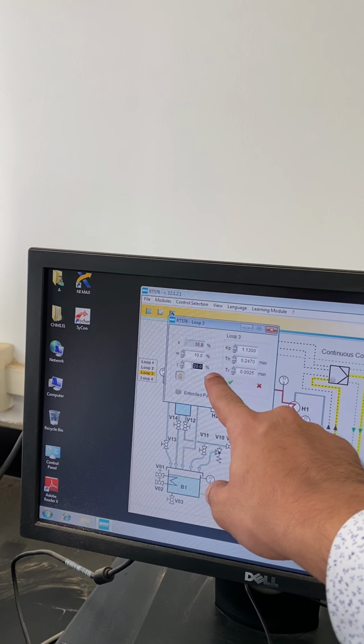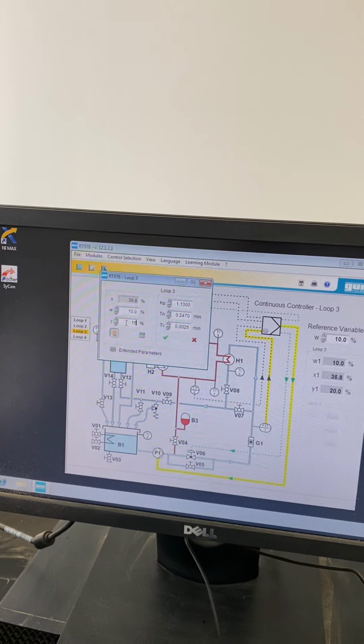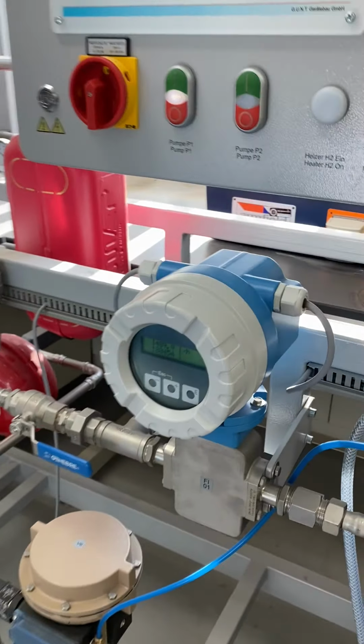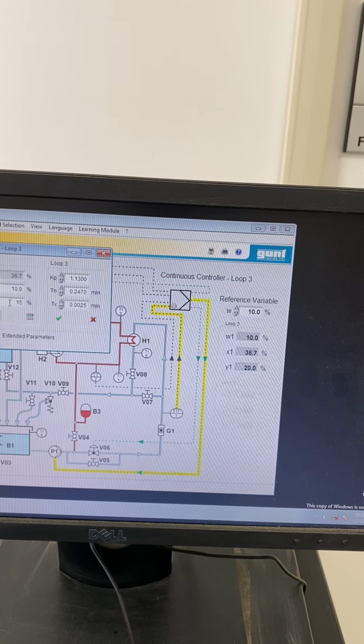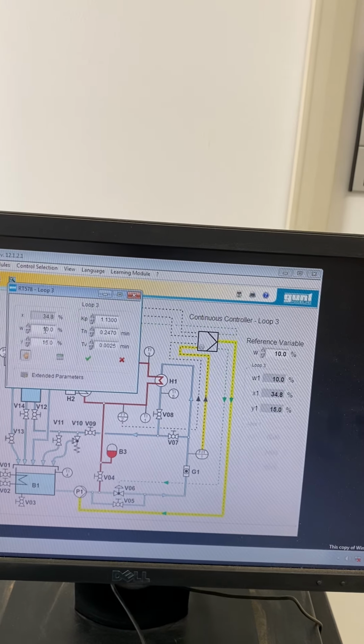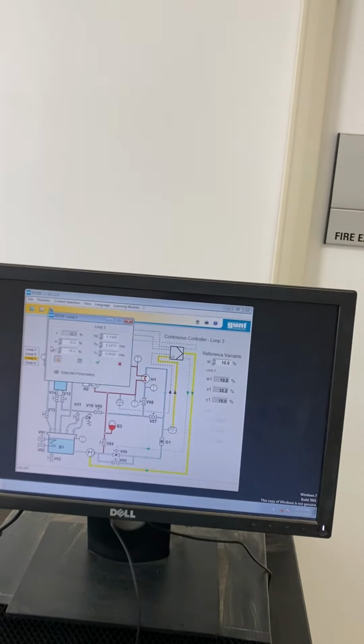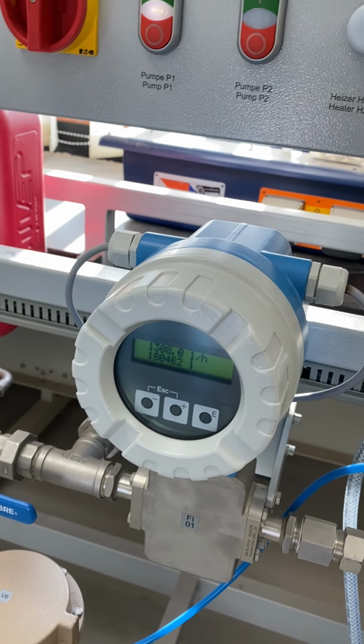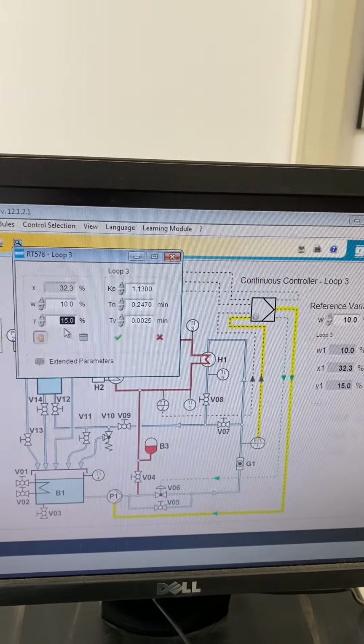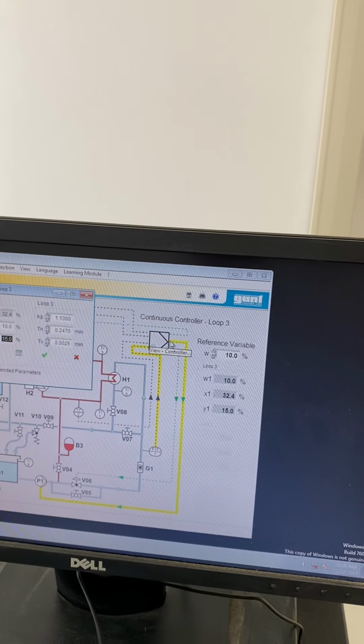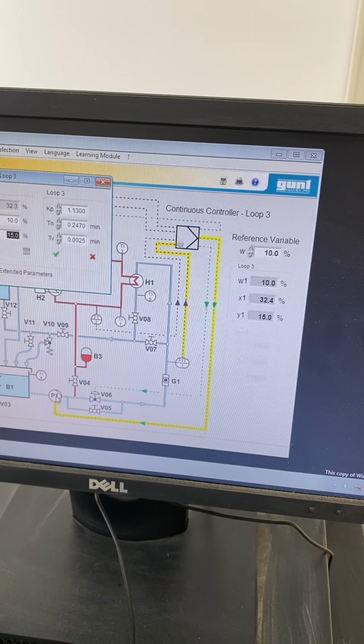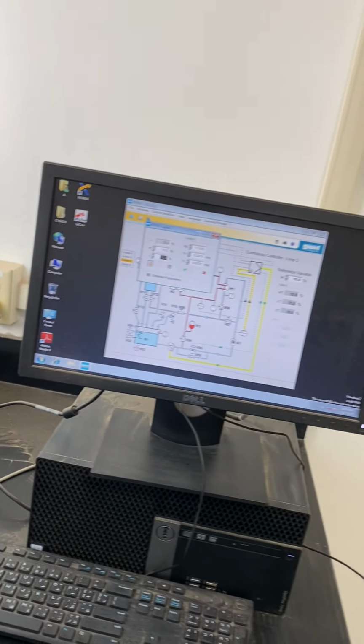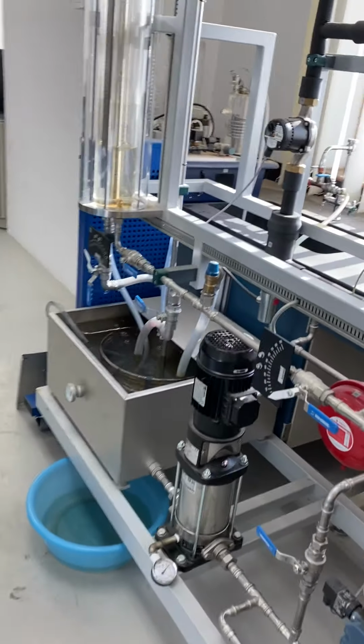So what I'm going to do here, Shabab, is change the signal that will go to the manipulated variable. So if I go down to 15%, before that, Shabab, let's look at the measured flow rate. It's around 1,500. Now the pump is my final control element. So if I go down from 20 to 15%, you're going to notice that the measured value right now is going down to around 32. Okay, the flow rate previously was around 1,500. Now it's around 1,300. When I made this change in the output signal, what happened exactly is that the output signal going from the controller, as you can see here, to the final control element, which is the pump, has been changed. I reduced the value of the output signal. So it's like telling the pump to reduce its speed.